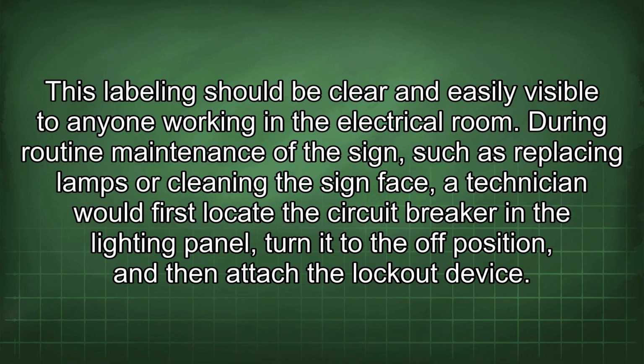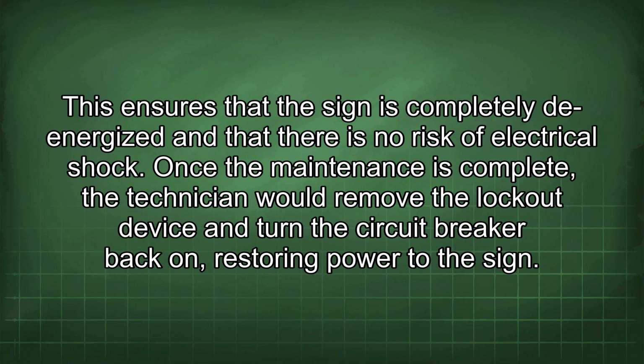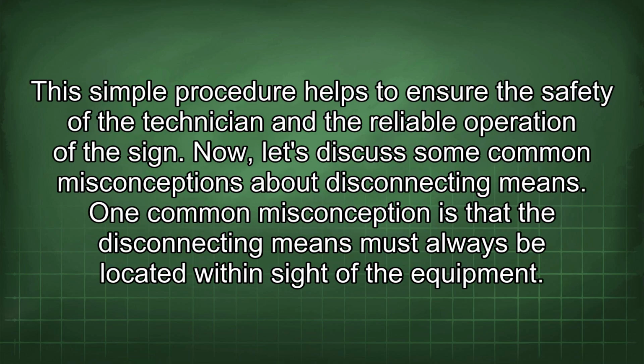During routine maintenance of the sign, such as replacing lamps or cleaning the sign face, a technician would first locate the circuit breaker in the lighting panel, turn it to the off position, and then attach the lockout device. This ensures that the sign is completely de-energized and that there is no risk of electrical shock. Once the maintenance is complete, the technician would remove the lockout device and turn the circuit breaker back on, restoring power to the sign. This simple procedure helps to ensure the safety of the technician and the reliable operation of the sign. Now let's discuss some common misconceptions about disconnecting means.